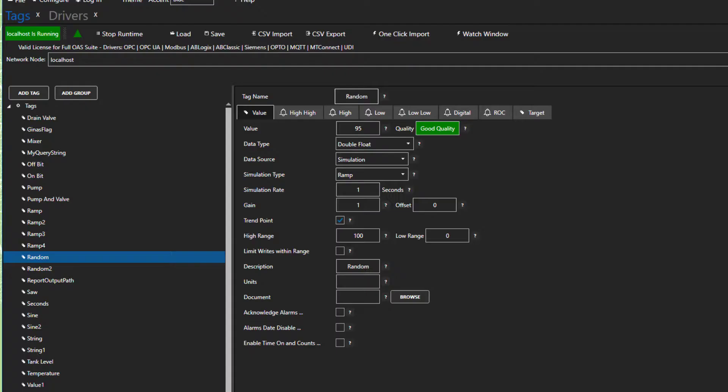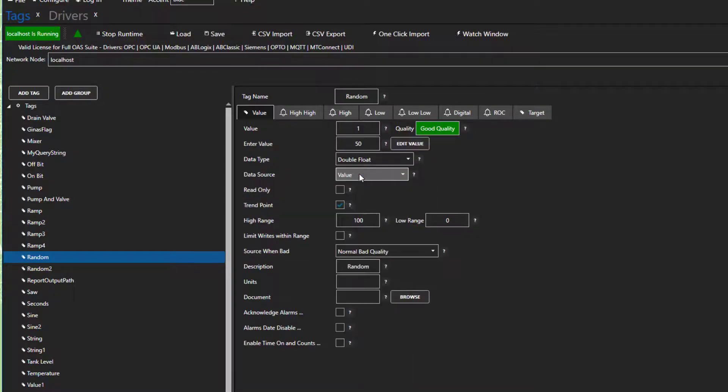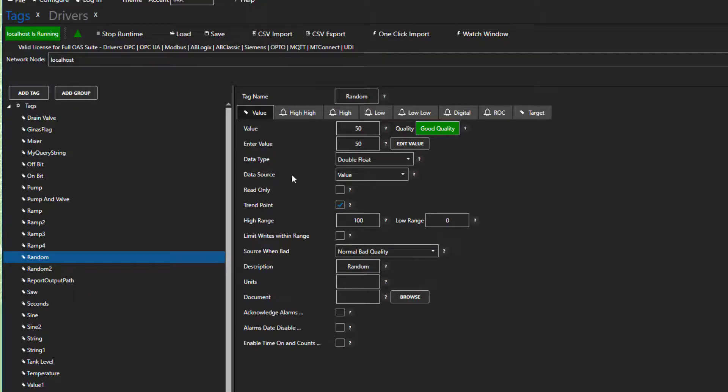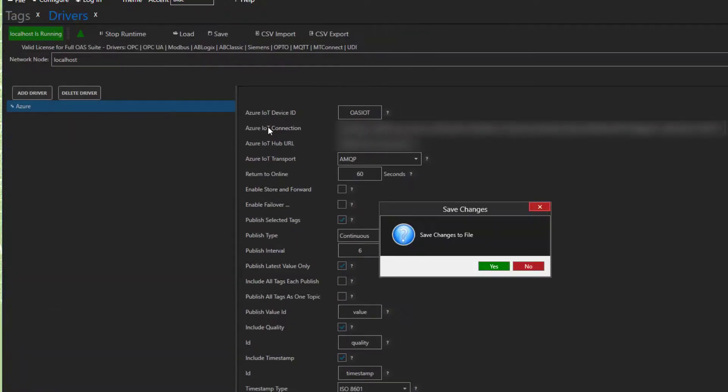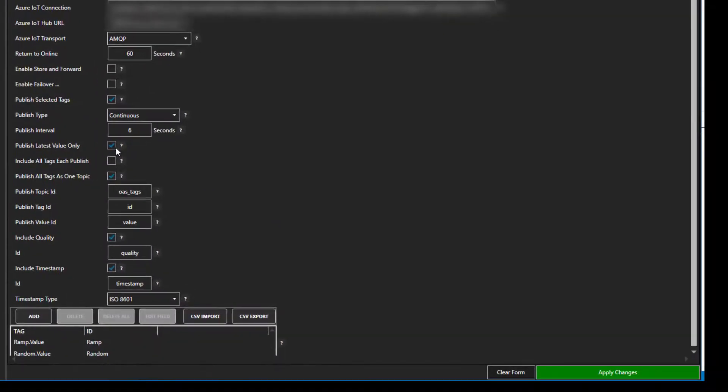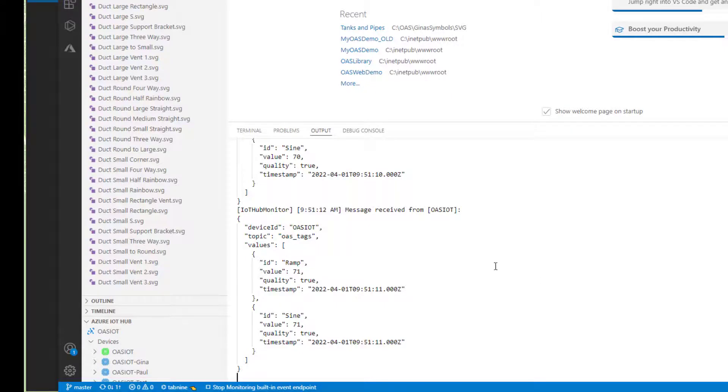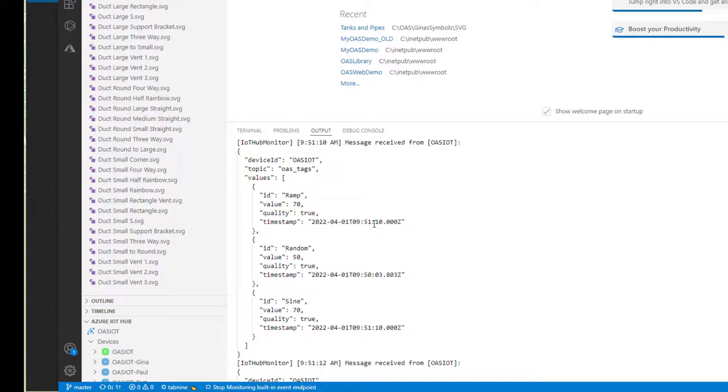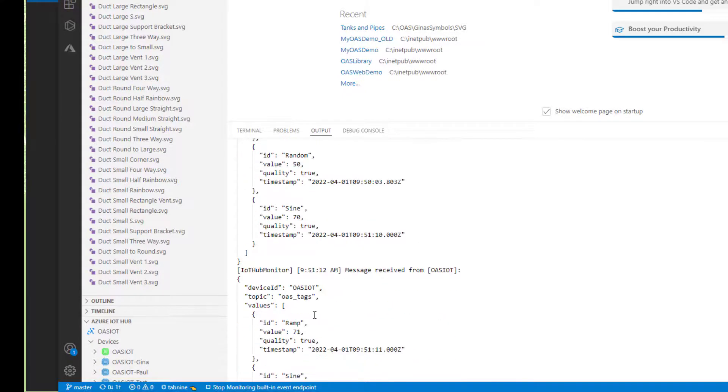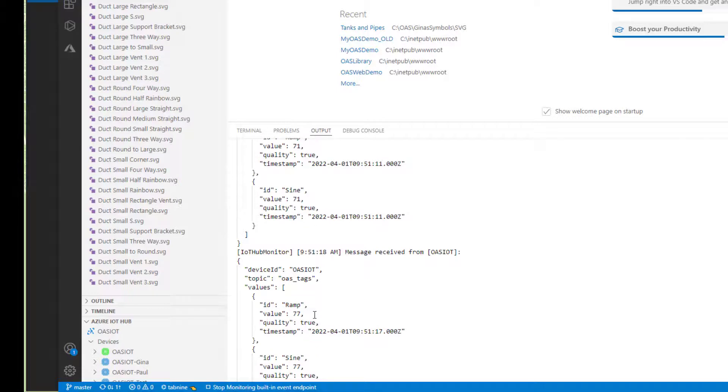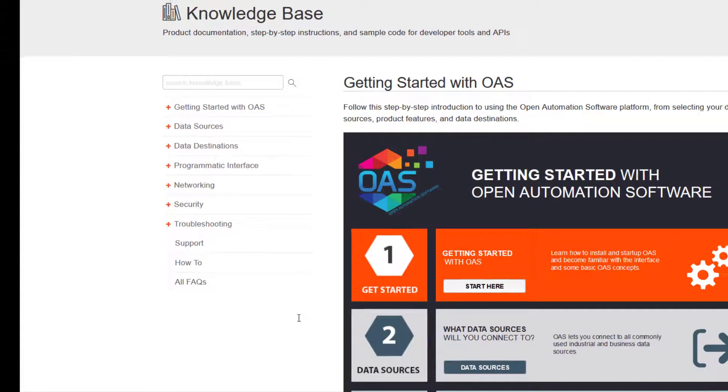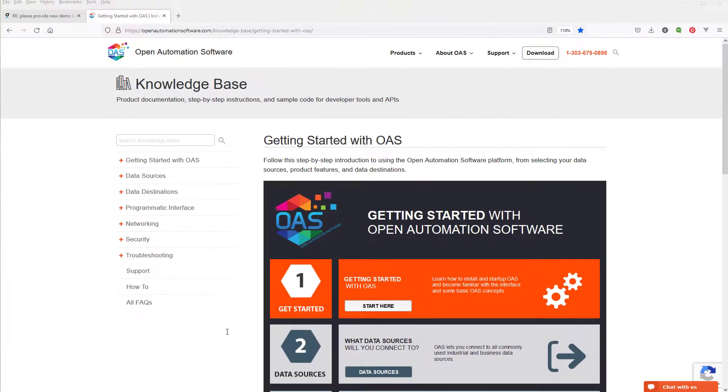Okay, let's look at one more setting. I am going to change my random tag to have a data source of value so that it won't change. I am going to check Publish All Tags as one topic again. We have Publish Latest value only checked. With it set this way, we should only get our random tag in the first publish. Let's apply our changes and go see. We can see that's exactly what happened. If we had included all tags in each publish, it would send the random tag each time despite its value not changing.